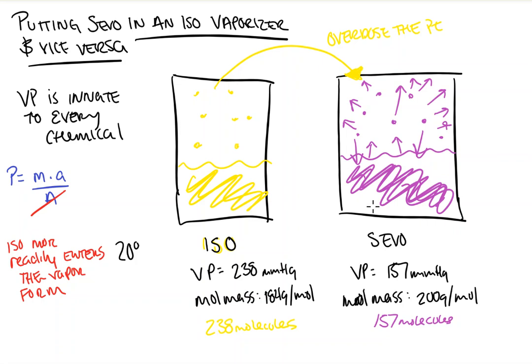Conversely, putting sevo into an iso vaporizer, you would underdose the patient — for the opposite reason. Sevo is harder to liberate from liquid to volatile gaseous form, and when you put it in a container calibrated for a molecule that more readily enters the vapor phase, it means it's going to have a harder time liberating those molecules from liquid to vapor.